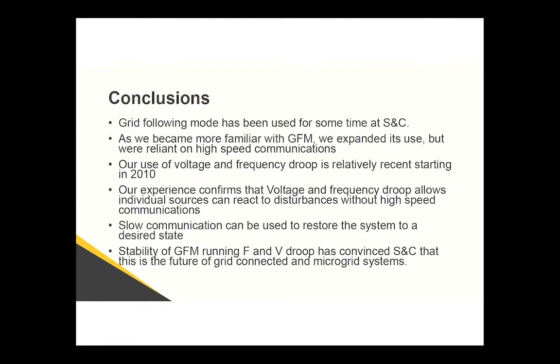The nice thing about using that type of system is the communication can be very slow. As we all know, communication can be problematic. We were pretty lucky because our systems were very tightly coupled, and so we use Ethernet communication, 100 megabit per second, to communicate between inverters. That all works really well, but that doesn't work so well as things get spread out on the system.